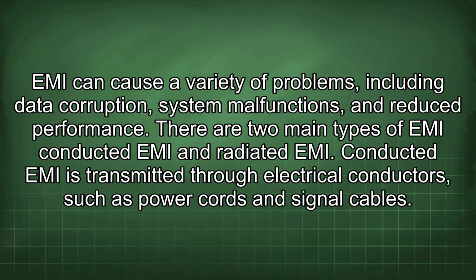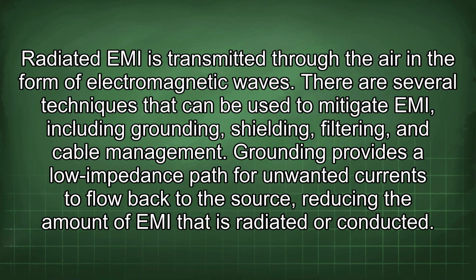Conducted EMI is transmitted through electrical conductors such as power cords and signal cables. Radiated EMI is transmitted through the air in the form of electromagnetic waves. There are several techniques that can be used to mitigate EMI, including grounding, shielding, filtering, and cable management. Grounding provides a low impedance path for unwanted currents to flow back to the source, reducing the amount of EMI that is radiated or conducted.